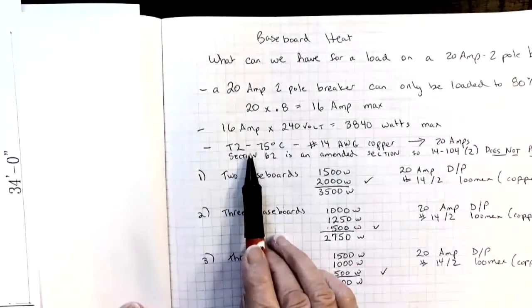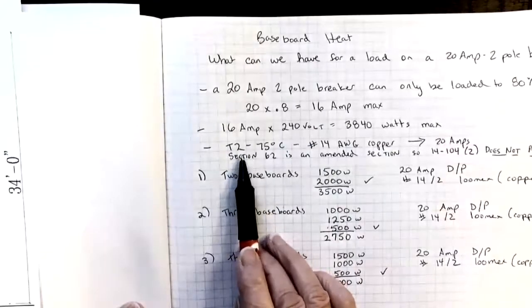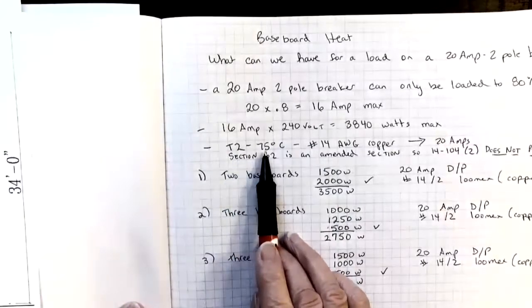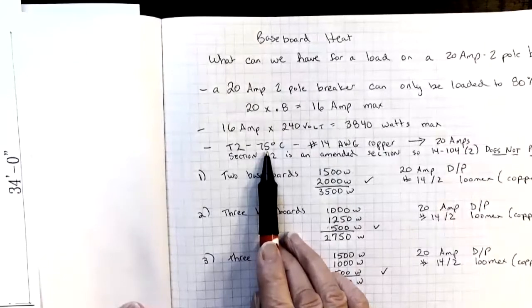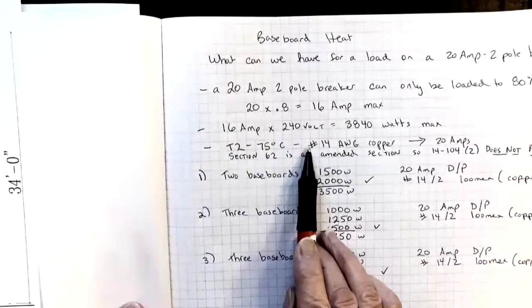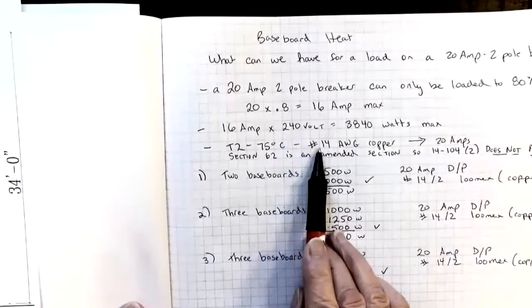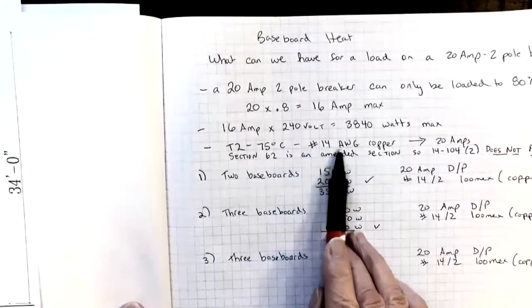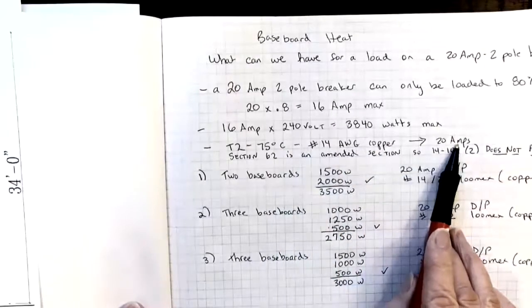The wire size that we would use on this 20 amp breaker comes from table two. And we're assuming that both the thermostat and the breaker and the baseboard heater all have a 75 degree terminal temperature rating. So table two 75 degree column tells us that number 14 AWG copper is good for 20 amps.